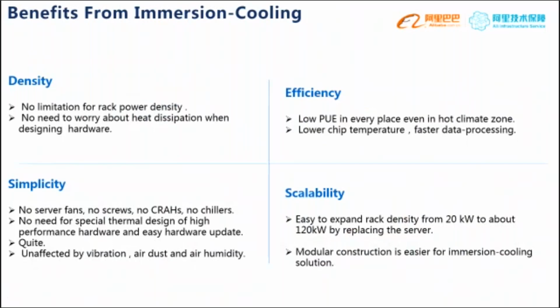The third is simplicity, because we don't need the chillers, CRACs, or server fans, so the whole cooling system becomes simpler. And this simplicity will improve the reliability of the cooling system. The fourth is scalability. In immersion cooling, it's easy to expand rack density from almost 20 kilowatt to about 120 kilowatt just by replacing these servers. And the modular construction is easier.